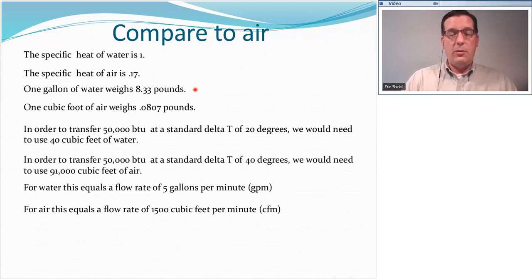1 gallon of water weighs 8.33 pounds. A cubic foot of air, which is our standard measurement of air, is 0.0807 pounds. This is why these two numbers are the way they are. Water, of course, is much more dense than air is. In order to transfer 50,000 BTU of heat energy at a standard delta T of 20 degrees, and when I say delta T, from now on, delta T means change in temperature. So at a delta T of 20 degrees, our water is changing temperature 20 degrees. We would need to use 40 cubic feet of water. We're going to have to move 40 cubic feet of water to move 50,000 BTU.